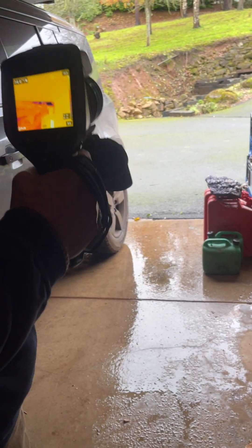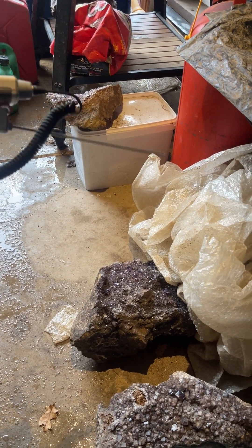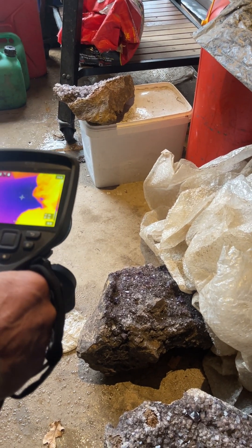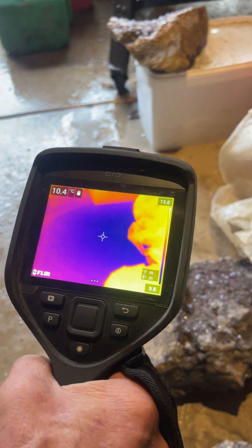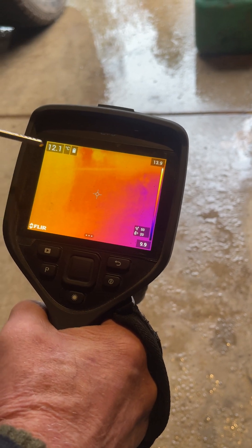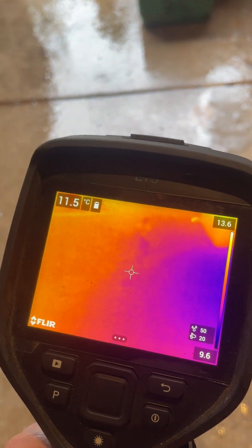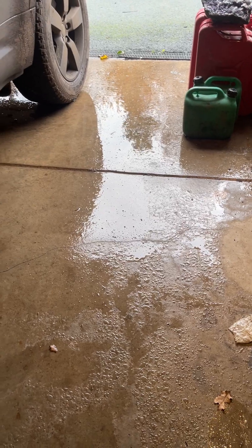So I said to Lucy, we need to get a little bit scientific about this, so I've got the imaging camera out. It's been a little bit blowy during the night, but this is interesting — there was some bubble wrap here from unwrapping our rocks, and it was covering and insulating the floor. That floor measurement there is 10.4°C, and where it's condensing at the moment it's 11.7. You can see on the imaging camera: 11.5, 11.4. So this is cold concrete.